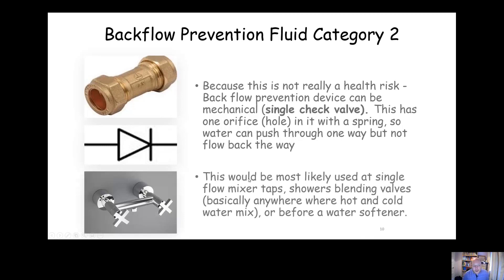Backflow prevention for fluid category two requires at least a single check valve to prevent that water flowing back. It's not really a hazard, but it's changed from the way it came in from the mains, so we need to prevent it flowing back into the mains. Anywhere hot and cold water mix — like a mixer tap or a shower — you should fit a single check valve as an absolute minimum on the cold, and if there's an imbalance in pressures, on the hot and cold.